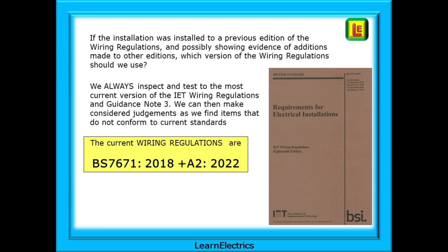One question that often pops up goes like this: if the installation was installed to a previous edition of the wiring regulations, and possibly showing evidence of additions, which version of the wiring regulations should we use? We — that's you and I, and any inspector — should always inspect and test to the most current version of the IET wiring regulations and Guidance Note 3. We can then make considered judgements as we find items that do not conform to current standards. The current wiring regulations are BS 7671 2018, Amendment 2 2022.